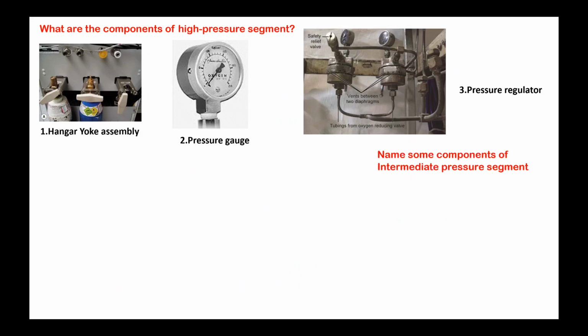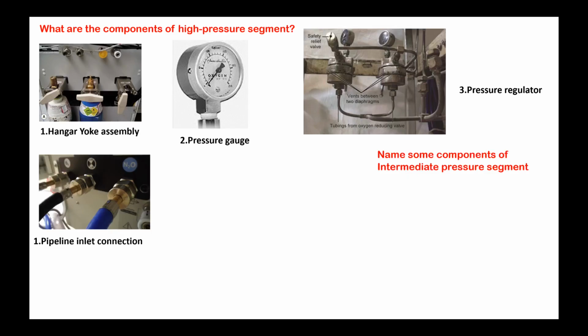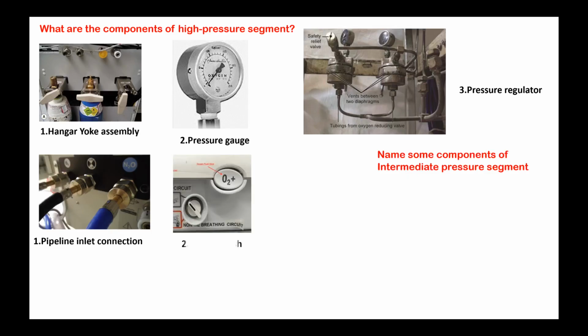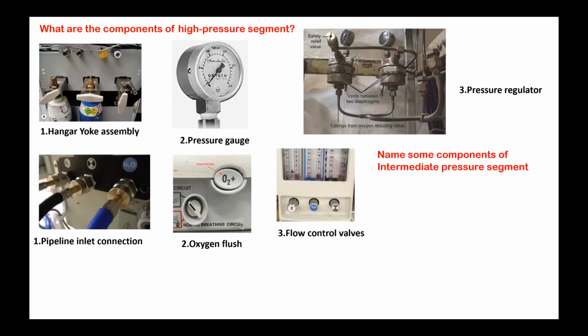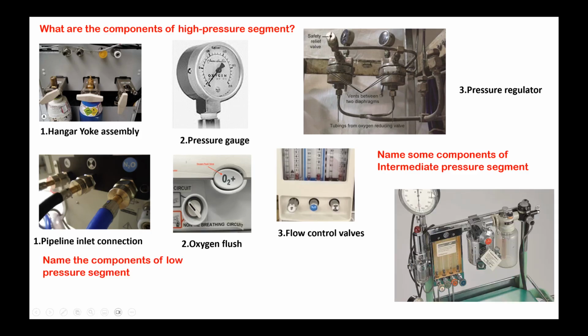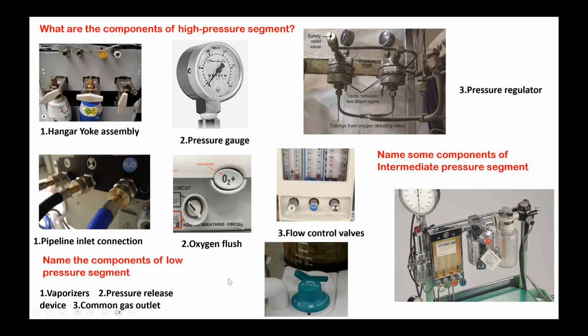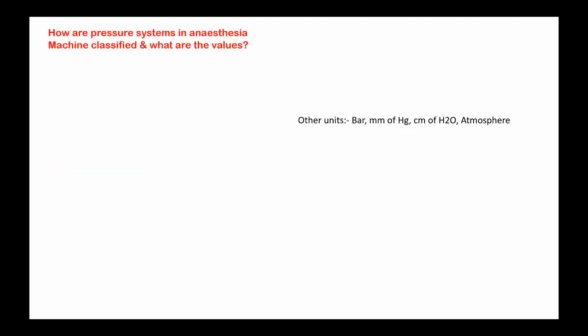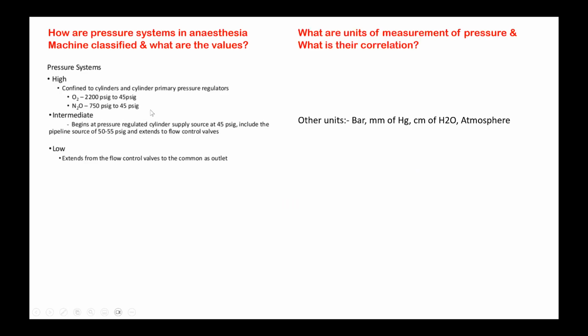Components of the intermediate pressure segment: pipeline inlet connection, oxygen flush, and flow control valves. Components of the low pressure segment: flow meter, vaporizer, pressure release device, and common gas outlet. They all come under the low pressure segment. How are the pressure systems in the anesthesia machine classified and what are their values? I've already seen that: high, intermediate, and low.